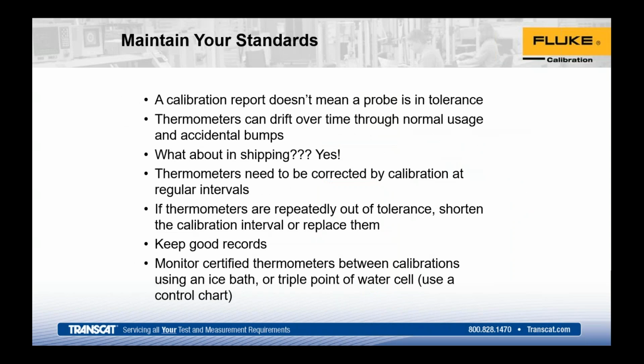All right, so now that we've talked through a few things, maintaining your standards. That's usually more of a consideration for your probes and your readouts. As we've talked about with some of the higher end probes, RTDs, PRTs, they are platinum winding. They do drift through normal use, so just time and use makes them drift. Also, physical vibrations, bumps, taps, or like a motor vibrating or tapping, that's going to make them drift quicker. So again, shipping, things like that, make sure you package them well if you're sending them out for service.